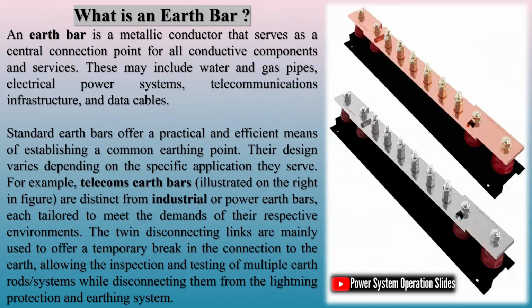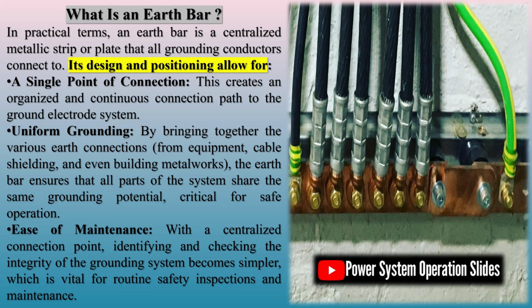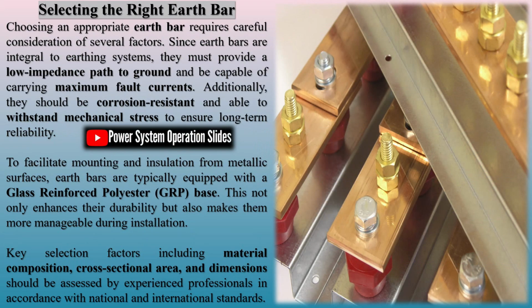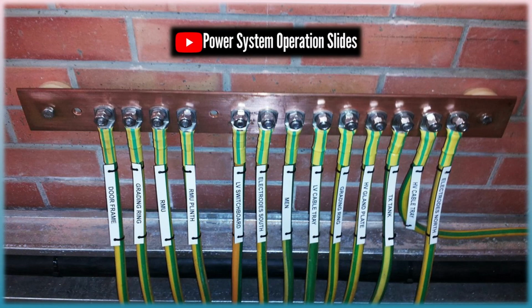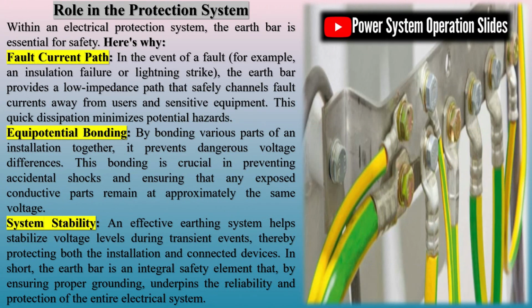Faults can arise at any point in the electrical network, with outdoor transmission lines being particularly vulnerable. These faults often result in extremely high currents. While power systems employ protective measures such as overcurrent and distance protection to respond to these faults, there can be brief moments where high current levels persist. These surges can cause dangerously high step and touch voltages, posing a safety hazard to nearby personnel. A critical mitigation strategy involves providing a low impedance path to ground, which helps minimize these risks effectively.